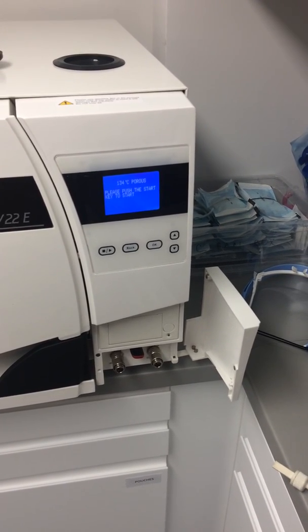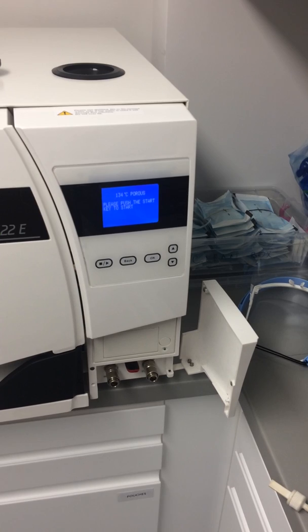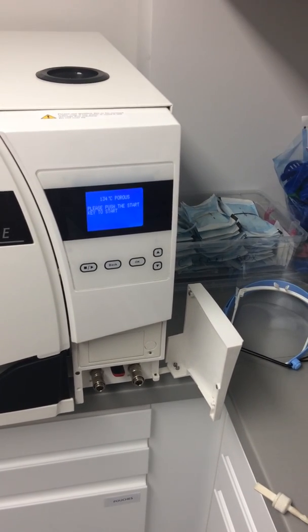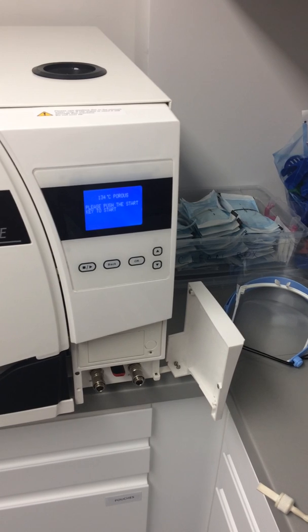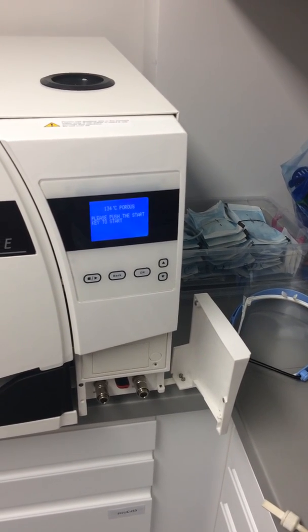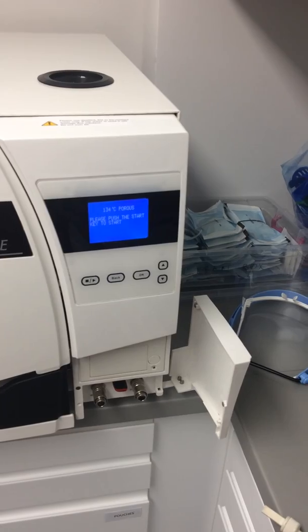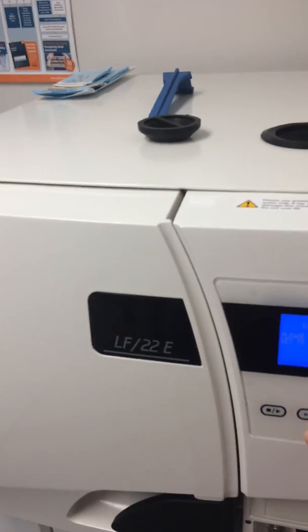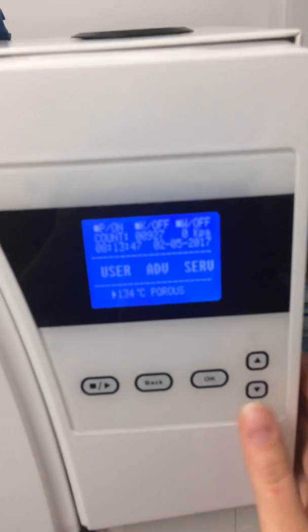Okay, there is one more test to be done. It's a vacuum test. Once a week, a nurse has to do it on an empty cycle. It is also called the air leakage test. So what we do, we go to the main menu, we go to user, and then there is a cycle vacuum test, which is number 9 on our system, and we say okay, and then we start the cycle.